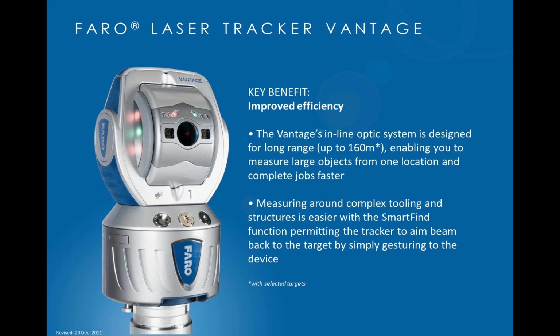And also a new feature with the Vantage is that we have a SmartFind technology on the system. SmartFind allows the user to gesture a reflector and the laser tracker will come and lock onto it. So it means that we don't have to be tracking 100% of the time. Whereas before, if you had an interruption in the beam, like somebody walking through it or an obstacle getting in the way of your measurements, you used to have to go back with the reflector, find the beam again and navigate your way through the obstacle. With SmartFind technology, we can simply go to where we want to measure and gesture to the Vantage tracker head, and it will come and find us.